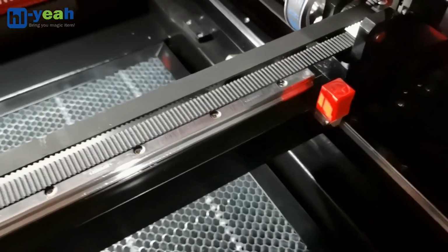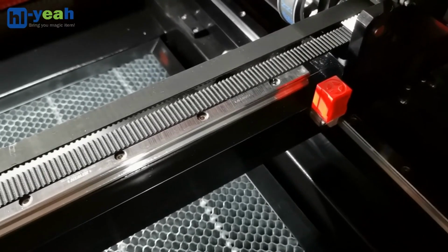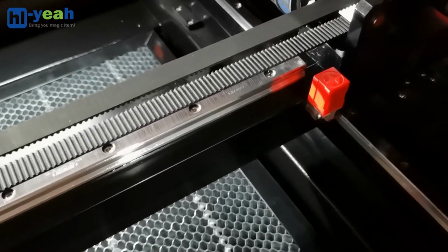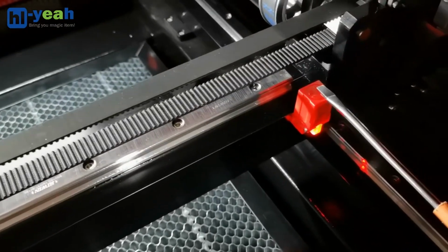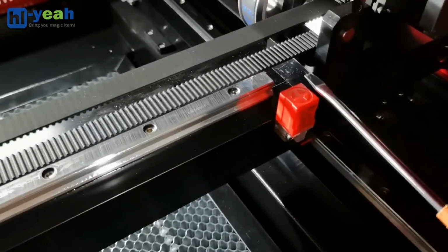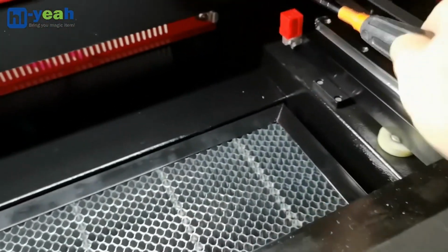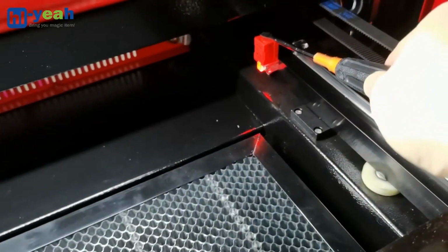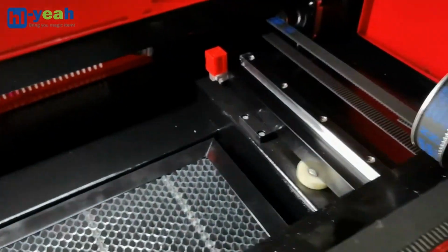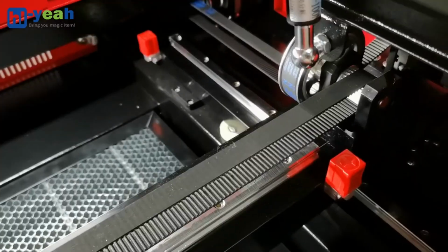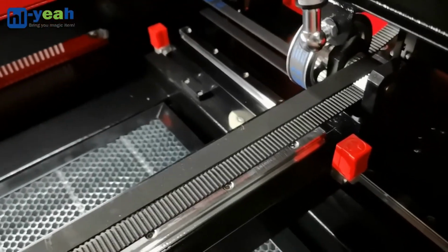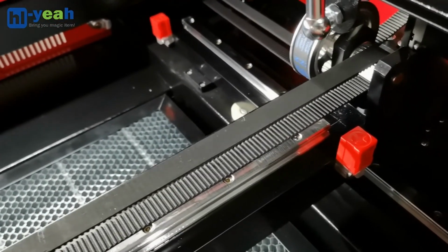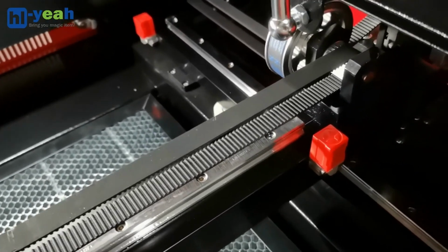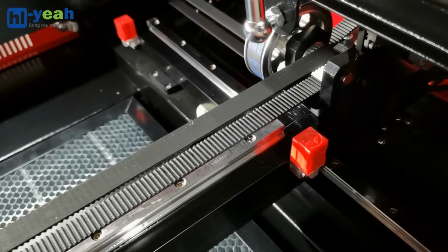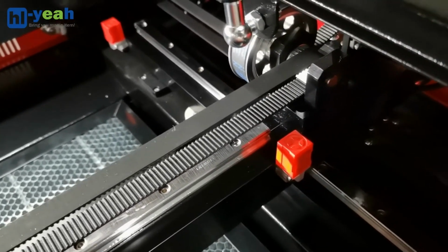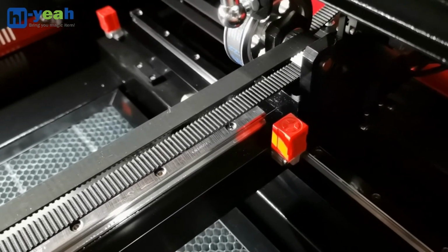In the homing process, when the laser head goes to the home position, the sensor will reflect and have the light. It's the same story on the Y homing sensor. If the laser head is hitting the X-axis or the Y-axis and they don't stop, that's because the homing process has an issue. Either homing sensor was not triggered correctly.